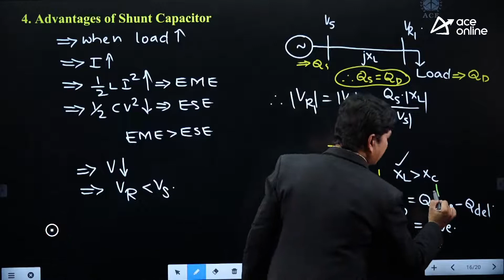Now in this one, QD is plus 10. As it is plus 10, we are getting VR1 less than that of Vs. If you reduce the positiveness of this one, reducing positiveness means if you are making it 9, then 220 minus 9, 211, increased. 220 minus 8, from 10 to 8 I have reduced the positiveness. So 212, 7, 213, 6, 214, 5, 215, like that. Whenever you are reducing the positiveness of the reactive power demand of the load, then automatically the receiving end voltage will be increased. Reducing the positiveness is nothing but increasing the negativeness.